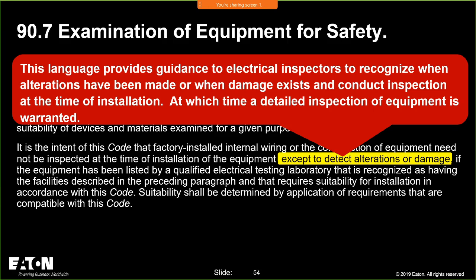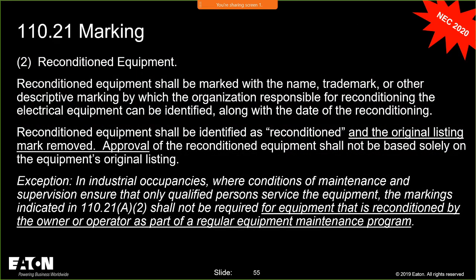Whenever you modify a piece of equipment in the field, you are going outside of how that product was listed and tested by the manufacturer, outside of the manufacturer's instructions. Then they're going to use 90.7 to say you need to get that looked at. Now, if you're following manufacturer's instructions, you can add ground bars and things like that. We sell accessories, all of that good stuff. If you're adding those accessories per manufacturer's instructions, that wouldn't be a modification that would flag them.